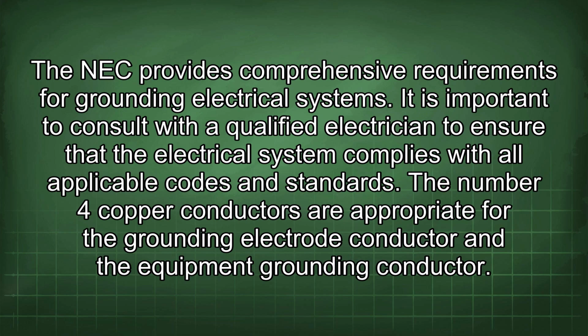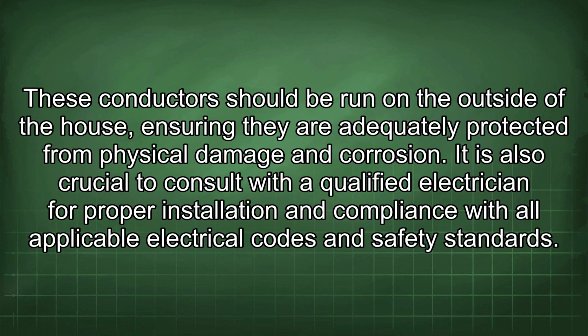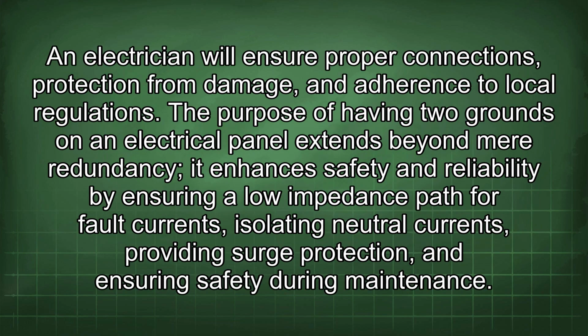and standards. The number 4 copper conductors are appropriate for the grounding electrode conductor and the equipment grounding conductor. These conductors should be run on the outside of the house, ensuring they are adequately protected from physical damage and corrosion. It is also crucial to consult with a qualified electrician for proper installation and compliance with all applicable electrical codes and safety standards. An electrician will ensure proper connections, protection from damage, and adherence to local regulations.